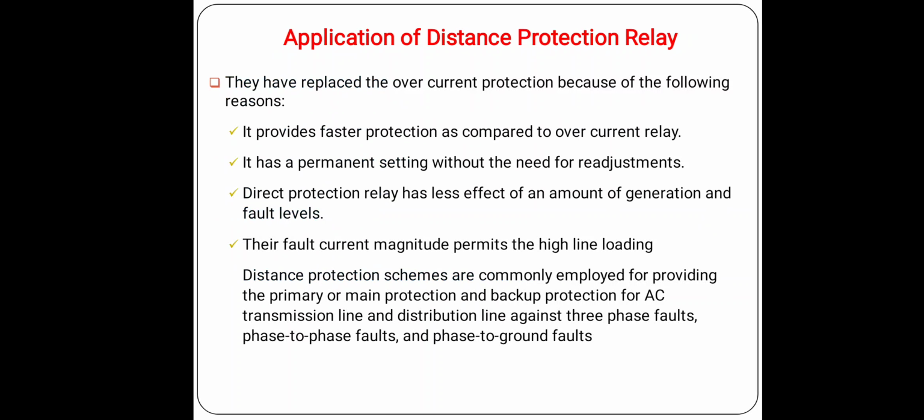So now next, the most important thing is, what is the application of the distance protection relay. Distance protection schemes are widely employed for the protection of high voltage AC transmission lines and distribution lines. They have replaced the overcurrent protection of the transmission line, as I said earlier, and the reasons are faster protection, simpler coordination, simpler application, permanent setting without need for readjustment, less effect of amount of generation and fault levels, and fault current magnitude permits high line loading.